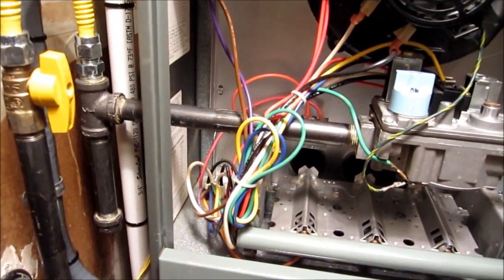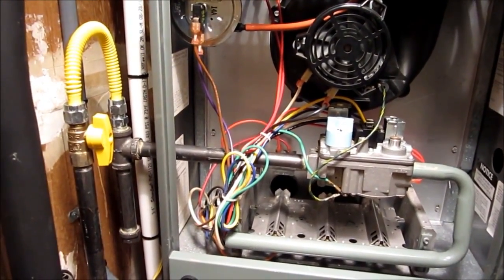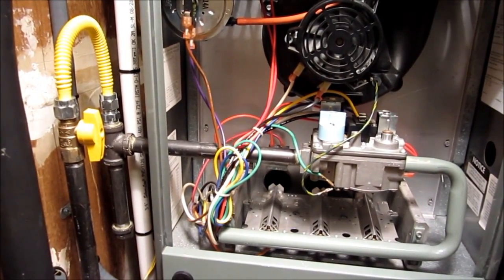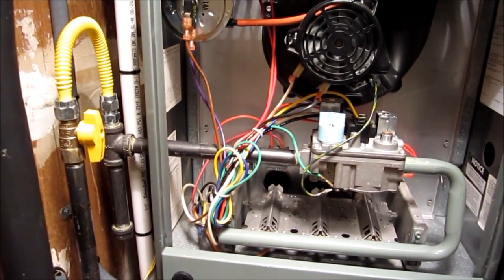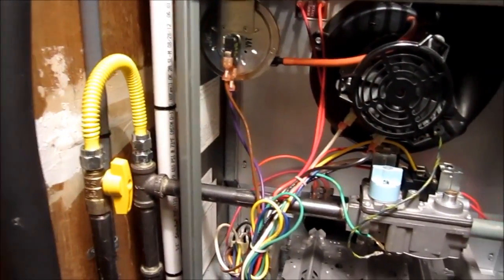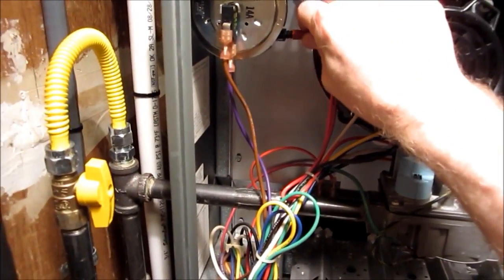Yes sir. On this particular furnace, this Rheem furnace, this is a negative pressure switch. Okay, so it's going to read negative. But nonetheless, let's go ahead and show people here how to set it up. The power is still off at the furnace, correct? Yes, it's still off. Okay, let's go ahead and pop it loose right there at the pressure switch, the little orange rubber hose there.